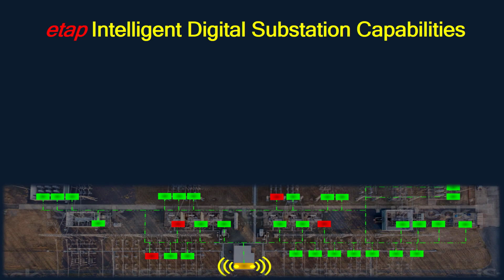The ETAP Intelligent Digital Substation goes beyond data acquisition, monitoring, and manual control. First, it uses ETAP's operational digital twin that allows validation of automation and operations. The digital twin provides complete details of the substation assets, which normally are not available in standard digital substation systems. This allows for quick decisions when locally performing work or operating the substation.